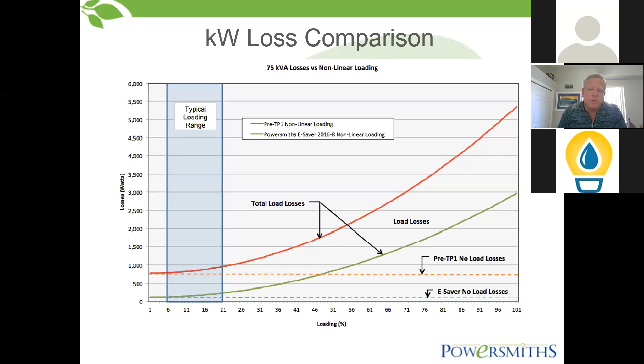This is the DOE data, linear versus electronic loads. You can see that the 35% loading figure isn't really true, and this is what we're seeing across the board. There are no linear loads out there anymore. You're not running heaters and resistors in your buildings, you're running computers and electronic ballasts and so forth. That's what you're running, not resistive heating.